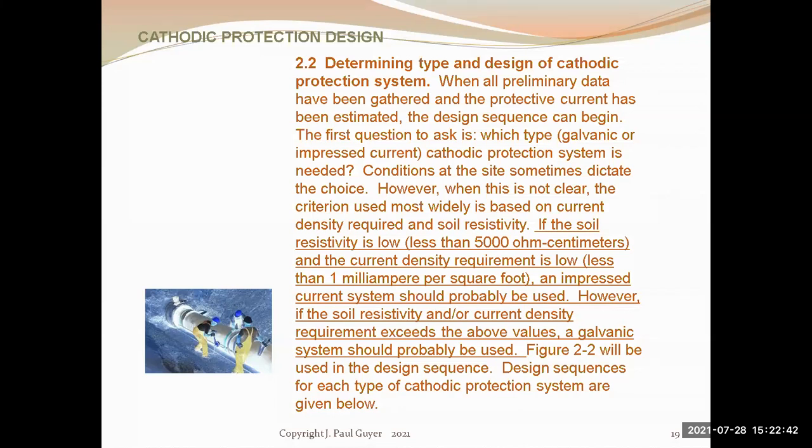But then the more resistive the soil is to the passage of current, then that becomes a less corrosive soil environment. So, there is a tipping point then. Basically, the soil resistivity runs from 0 ohm centimeters up to over 30,000 ohm centimeters.